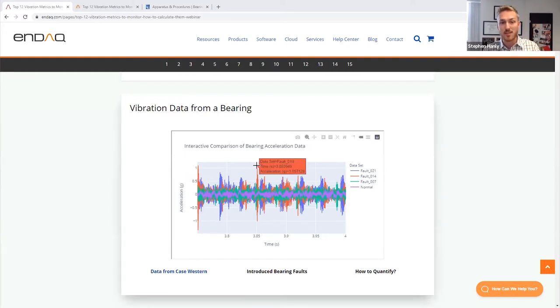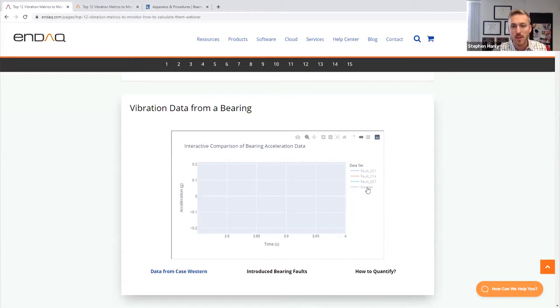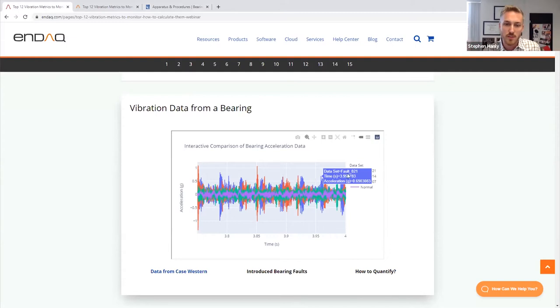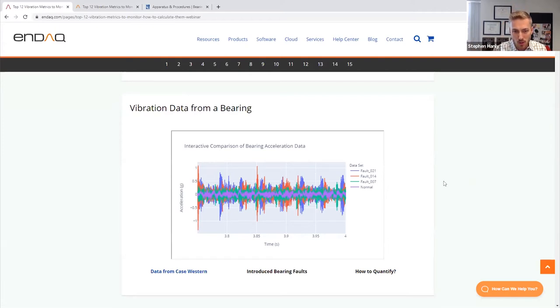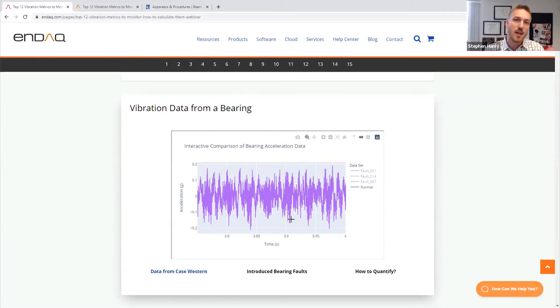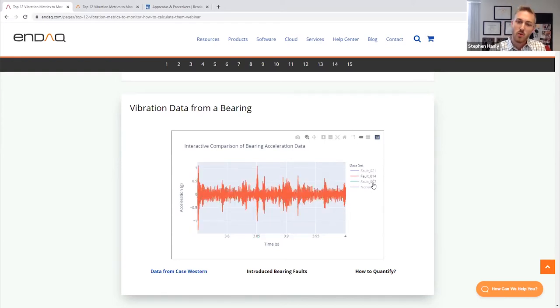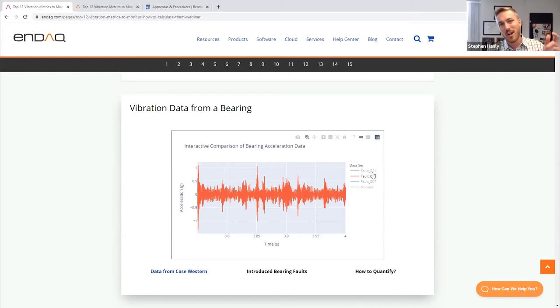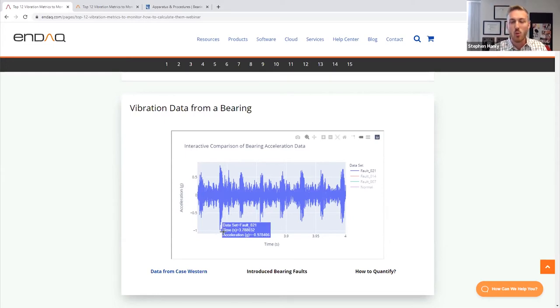Here's the bearing data. In this interactive plot you can zoom around, isolate one signal by double-clicking it, or turn off a signal. Looking in the time domain, the first thing people do is look at the peak acceleration. The normal bearing has a peak around 0.2 G's, the first fault condition has a peak of maybe 0.6 G's, the 14-mil bearing has a larger peak over 1 G — about 1.3 — and then interestingly, fault 21, which is a worse fault with a larger hole, actually shows a lower acceleration peak of about 1 G compared to 1.3 for the smaller fault.